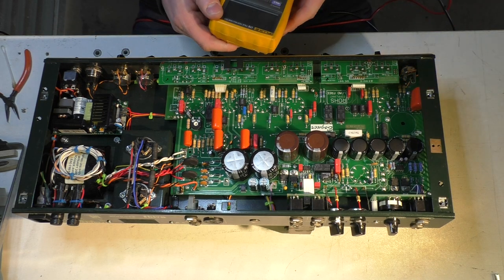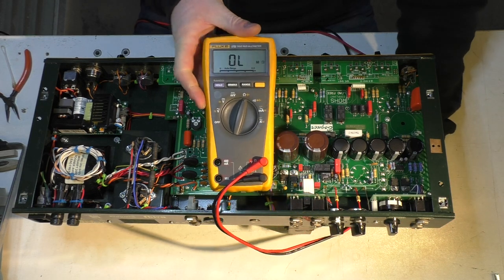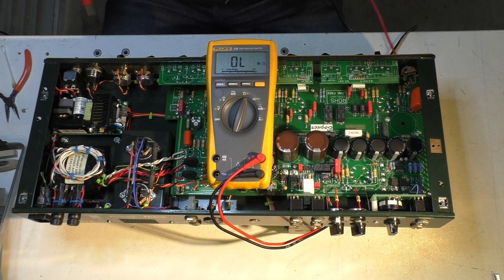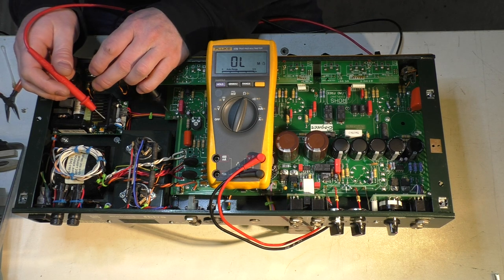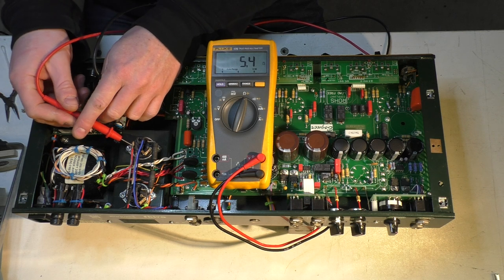But I flicked it on just to test, and of course nothing's as simple as just a simple service. There's always something that needs attention. So here I'm measuring from a ground test point to the cathodes. Both of them are paralleled, both output valves getting 5.4 ohms.